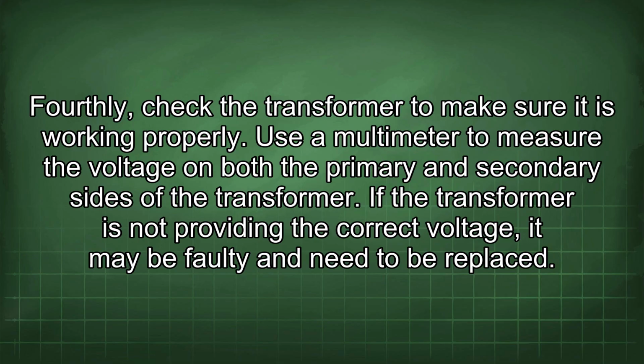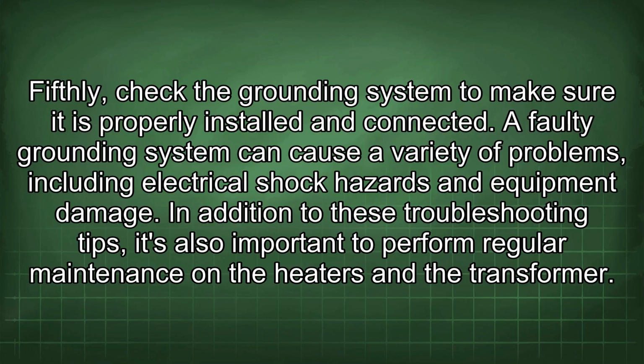Fourthly, check the transformer to make sure it is working properly. Use a multimeter to measure the voltage on both the primary and secondary sides of the transformer. If the transformer is not providing the correct voltage, it may be faulty and need to be replaced. Fifthly, check the grounding system to make sure it is properly installed and connected. A faulty grounding system can cause a variety of problems, including electrical shock hazards and equipment damage.